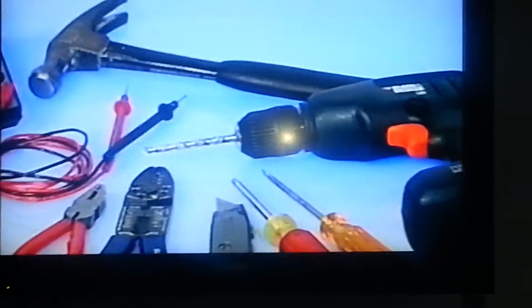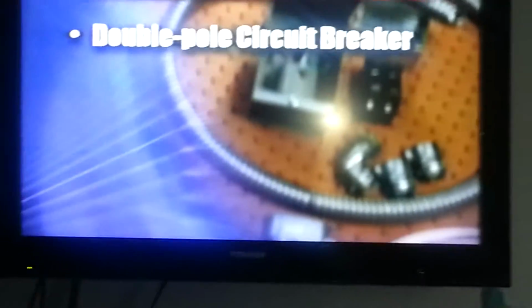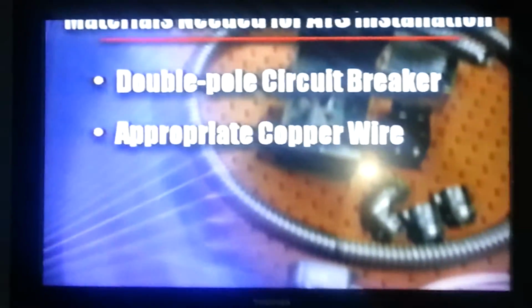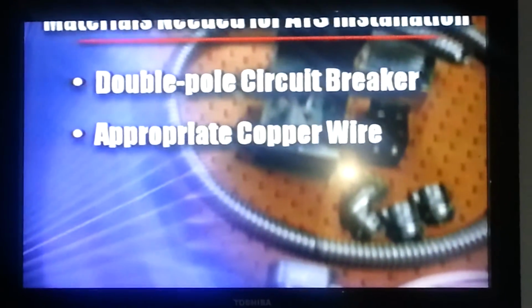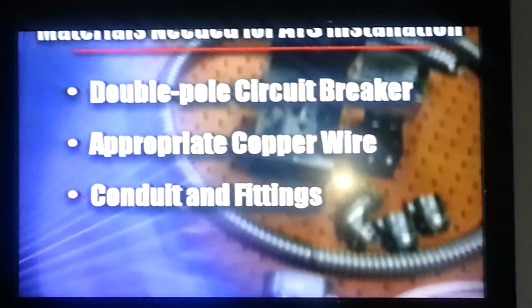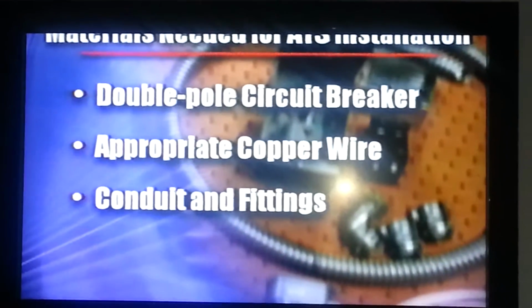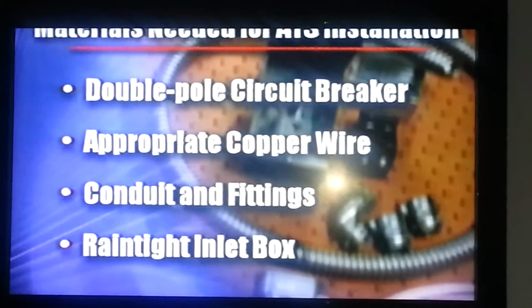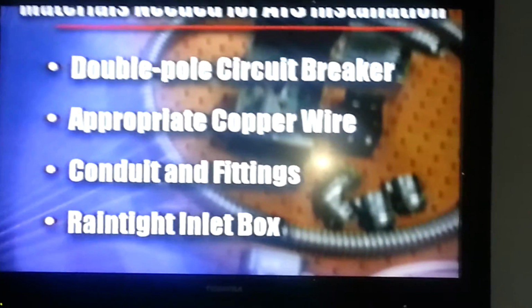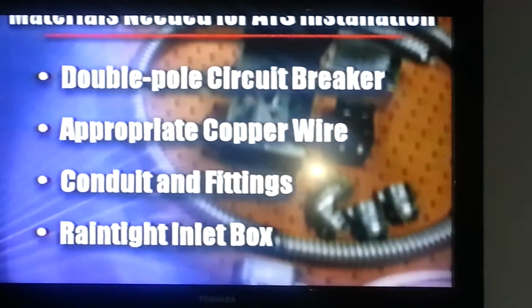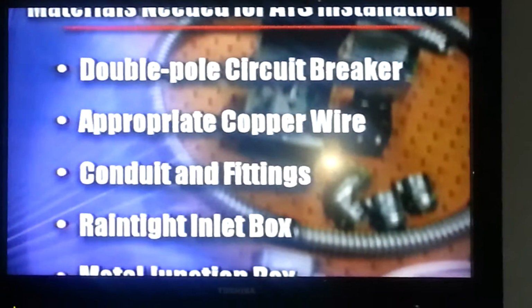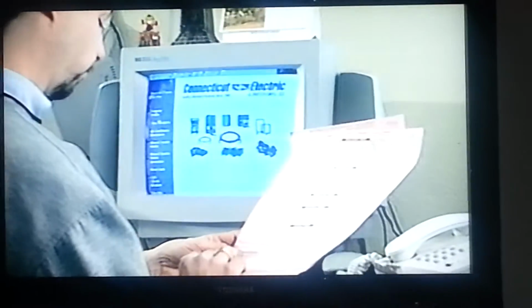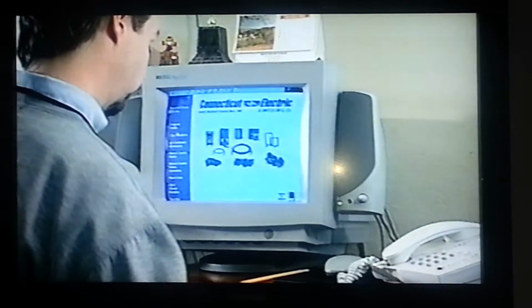In addition to the necessary tools, you will need the following materials to install the ATS: a double pole breaker to match the amperage of your manual transfer switch, appropriate sized copper wire for the amperage of your breaker, plus conduit and fittings suitable for your electrical system. Keep in mind that you may also need a rain-tight inlet box for your generator cable, and a metal junction box, depending on the configuration of your electrical system connection.